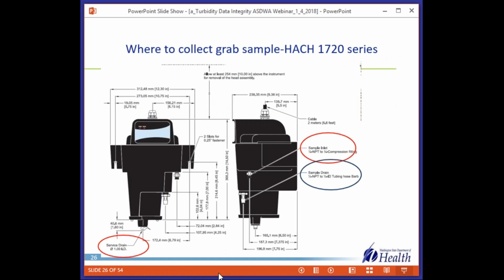So most of our systems had 1720D or E turbidimeters that look like this. So you have basically three choices. You can take the sample from the service drain, but usually that would cause a lot of sediment, so that's not a good one. You could go with the sample inlet right there, or you could go with the sample drain. So the sample inlet is before the bubble trap. So if you have bubbles in your water, that's not the best place. You can also cause some disruption in the flow that can impact the reading. So we think that the sample drain is actually the best place to take the grab sample. Number one, because it's gone through the bubble trap, and number two, because you're not going to disturb the flow of the sample, provided that you have this all set up right.